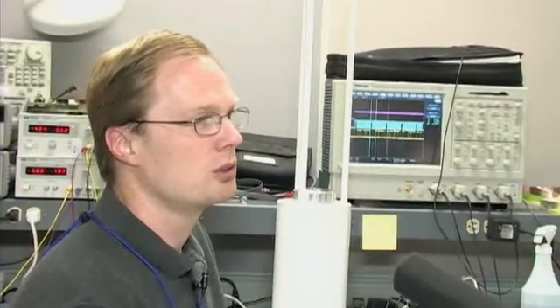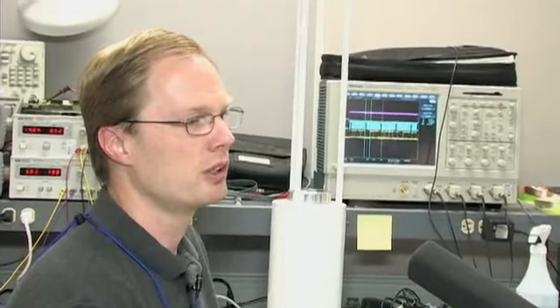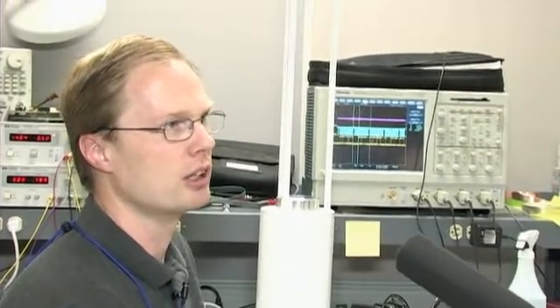Here's Brad Renschke working on another LiCOR product. He's a principal engineer here at LiCOR. We've heard about the portability and the purpose of this new LiCOR product. Can you tell us a little bit about the technology? We designed the LI-7700 specifically to suit the eddy covariance market, and what that means is we used an open-path design and chose a very low-power design strategy using WMS — Wavelength Modulation Spectroscopy. WMS is one of several spectroscopic methods to measure gas in the atmosphere. We chose WMS because it lets us use shorter path length and less reflective optics, really enabling the open-path design. And since it uses the shorter optical path, we can also minimize our thermal regulation.